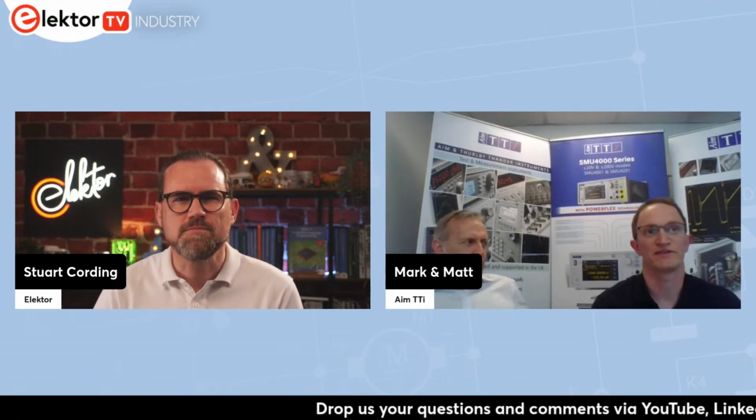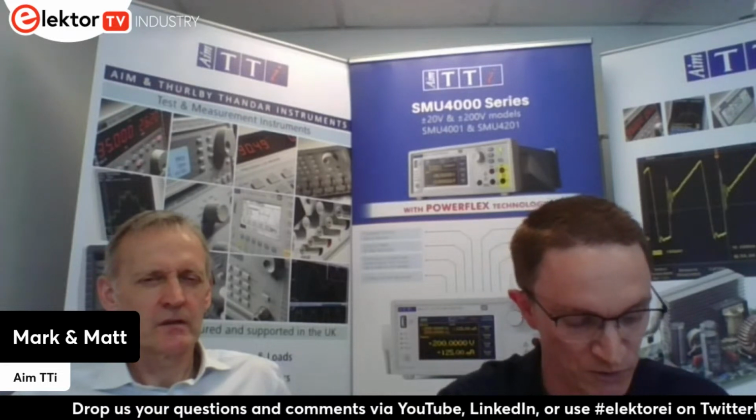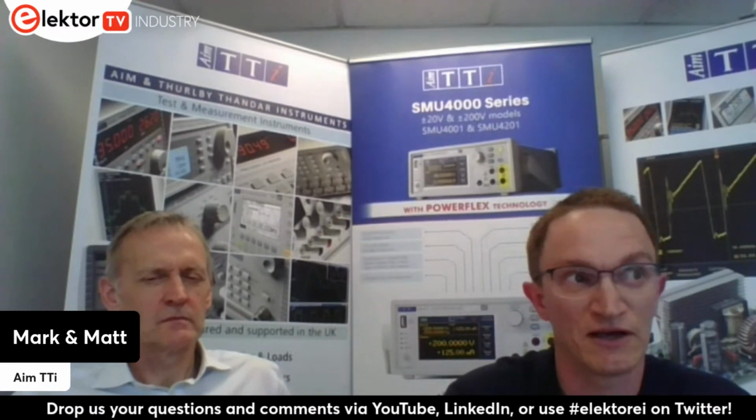Well, this, with any SMU development, has been a real push, because like Mark mentioned at the start, with our traditional power supplies we're looking at a very slow, stable output, whereas an SMU is a fast, reactive output. So we're really pushing for sub-millisecond response times. For example, the source voltage we spec typically around 300 microseconds, regardless of range and setting, to reach a stable level. Along with that, our measurement speed is 200 microseconds. So you're talking sub-milliseconds to not only reach the level and be stable, but also to get a measurement at that level, ready to move on to the next level.